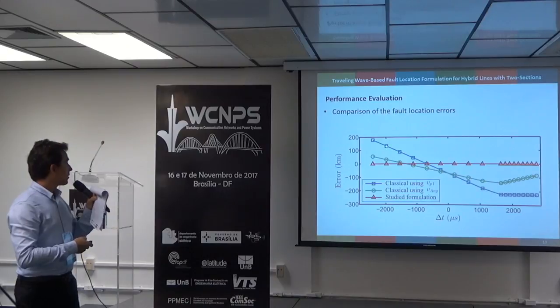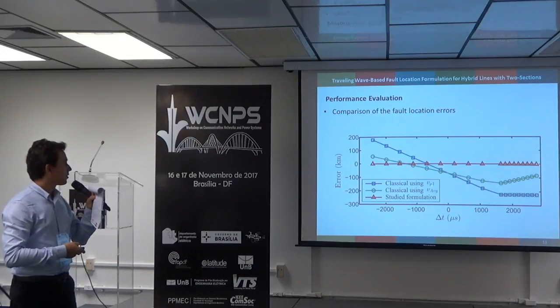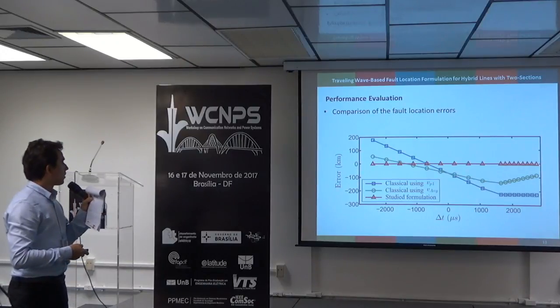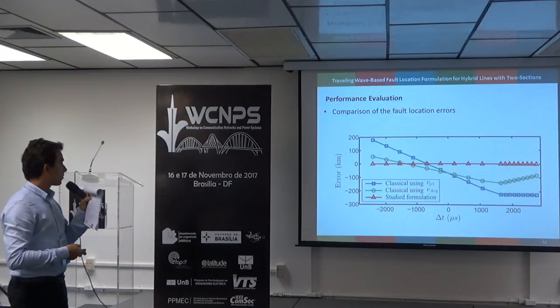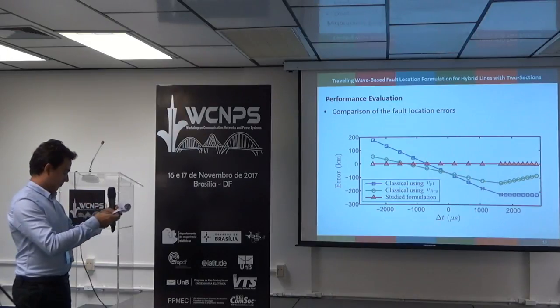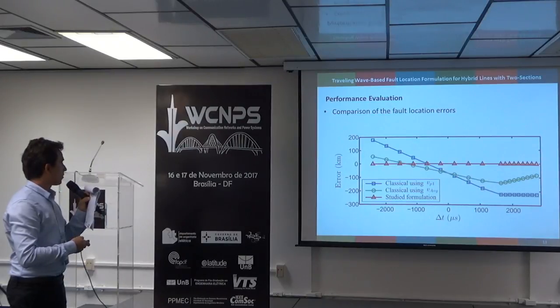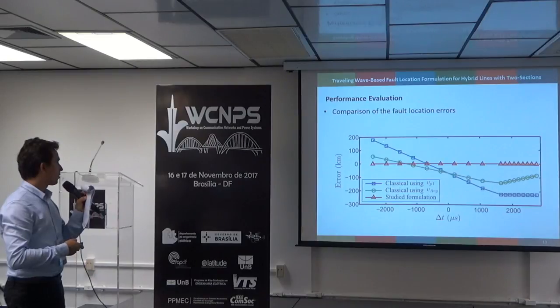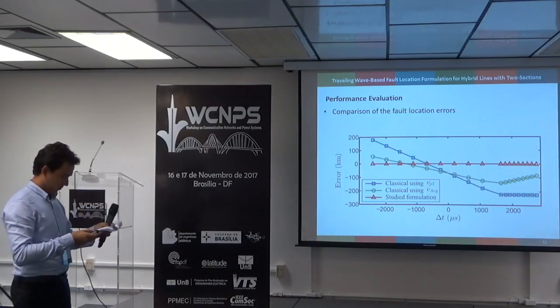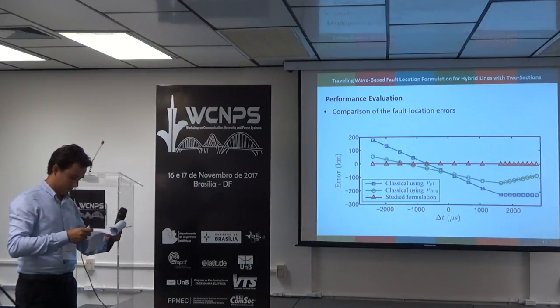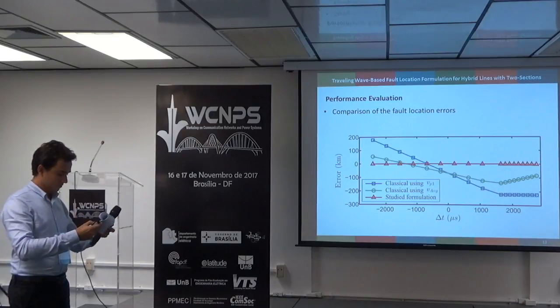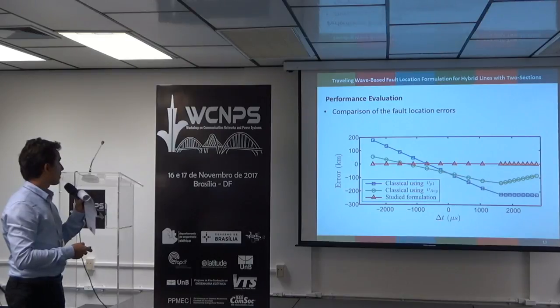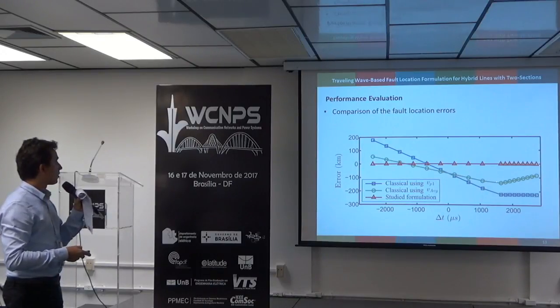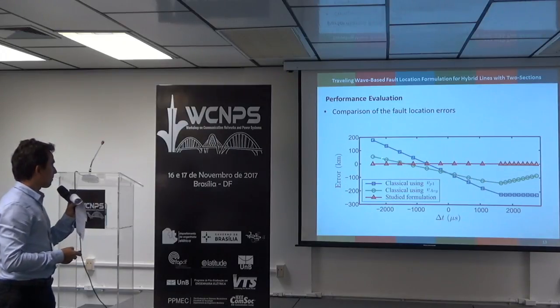On the other hand, applying the classical method using uniform velocity, VP1, the propagation velocity of section 1, or the average velocity between section 1 and section 2, the results completely diverge, with errors of about 200 kilometers. The use of the average velocity reduces the error, but does not provide accurate fault location.